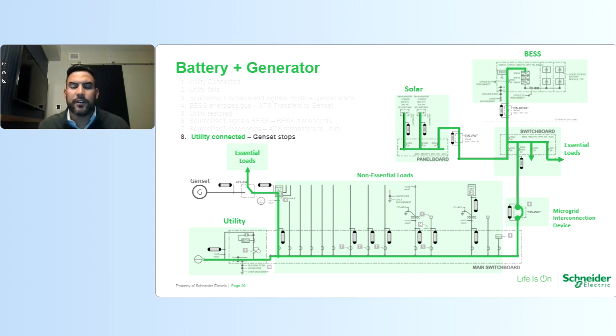The solar system here is very dependent on an anchor resource, and it relies on a consistent generator source, a utility, or a battery to provide steady voltage and frequency to parallel operate in grid interactive mode. So solar by itself cannot provide emergency power for most commercial applications. It's using an energy storage system or some type of generator system that provides that emergency power for your facility. And then of course you have the option to parallel solar, parallel generator with that. There's different ways we can configure this. This is more of a simple microgrid system to enable resiliency.